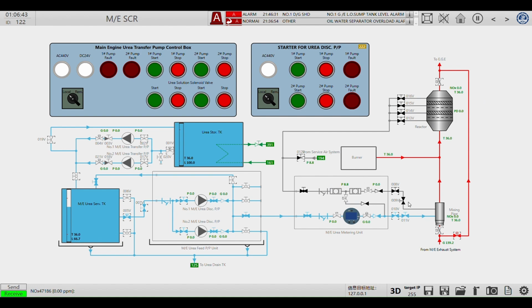So here is this catalyst system. We inject urea from here. This is a bypass valve where the system will be running. Basically the main engine has to run at a certain condition, certain load and certain exhaust temperature. This burner is to increase the exhaust temperature for the reaction to take place here. This air is for soot blowing this mixing pipe and this catalyst element over here.